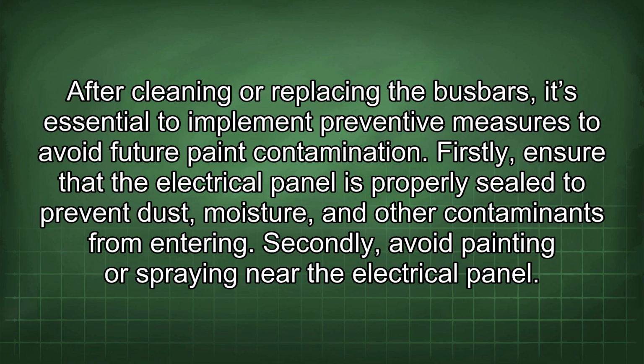After cleaning or replacing the busbars, it's essential to implement preventive measures to avoid future paint contamination. Firstly, ensure that the electrical panel is properly sealed to prevent dust, moisture, and other contaminants from entering. Secondly, avoid painting or spraying near the electrical panel.